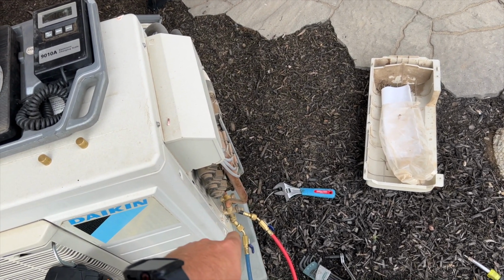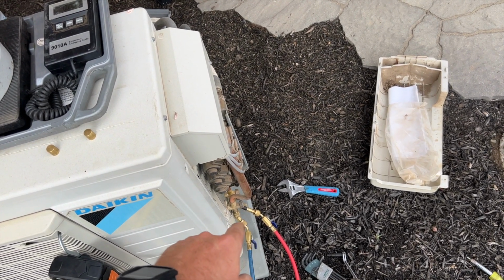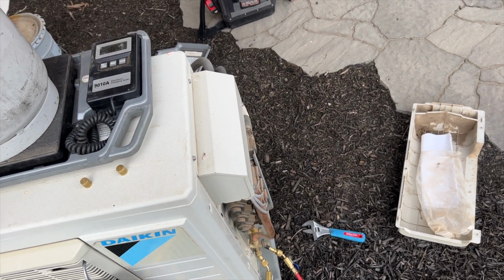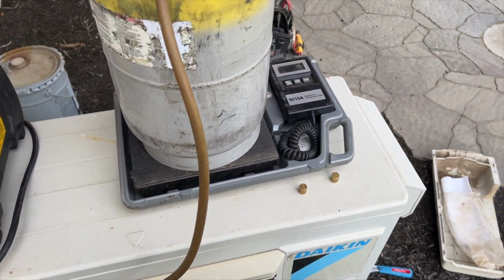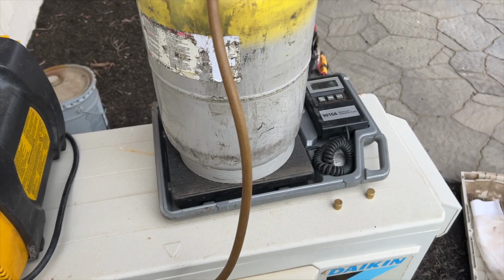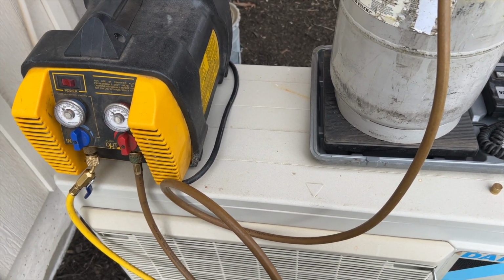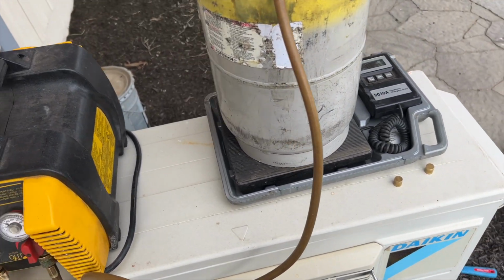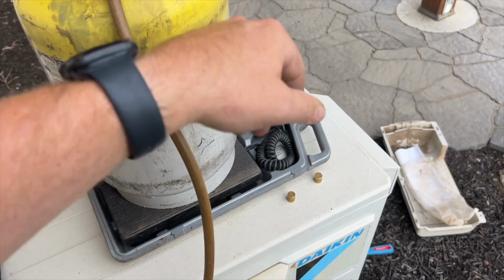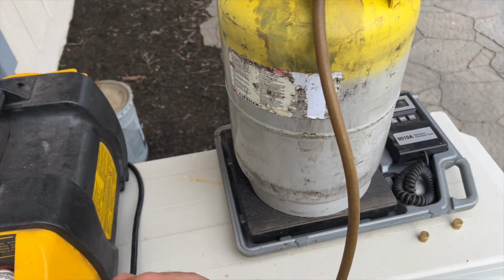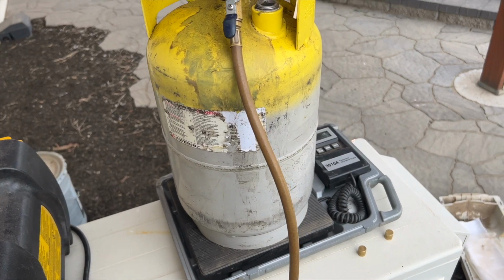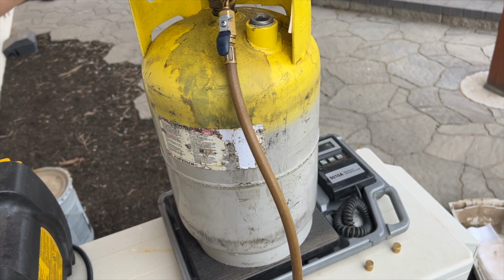I'm just going to recover the refrigerant in the line set, save time on my vacuum because it's a 2-head system, because we have to remove the heat exchanger on the indoor head in order to get to the blower motor. So we're going to go ahead and recover what's in the line set, and I'm going to weigh it. That way I know exactly how much I took out so we can keep the charge proper.